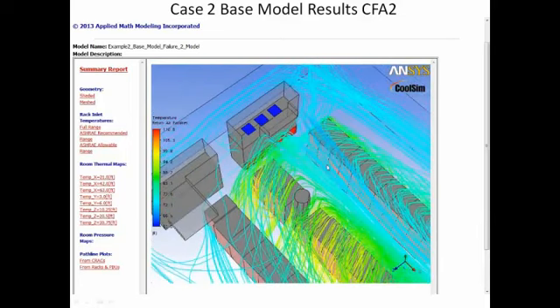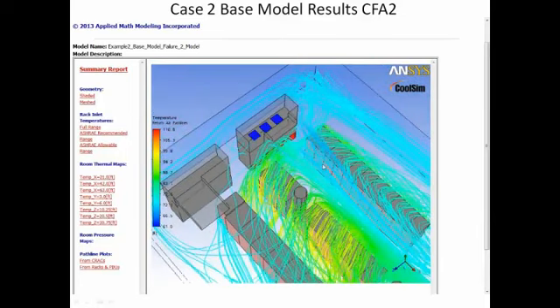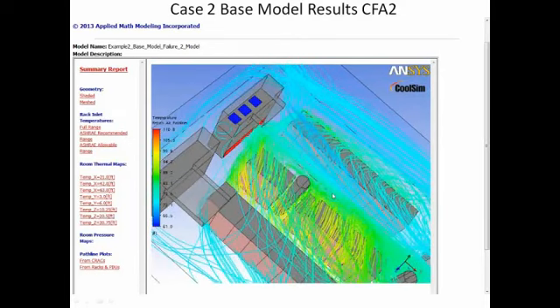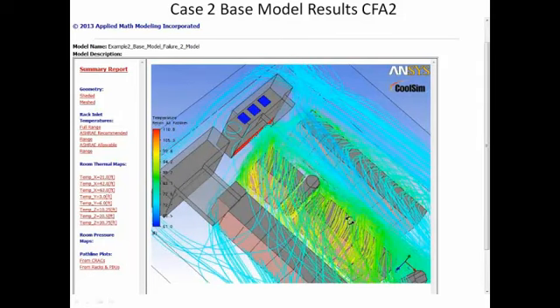One of the things that I've noticed in non-raised floor data centers is the returns are often the problems, because as design engineers, we often think of, well, let's get the cold air to the racks. But just as important is getting the hot air back to its proper place. Like you mentioned earlier, you should line up your hot aisles with the returns of the CRAC units so that they can breathe.